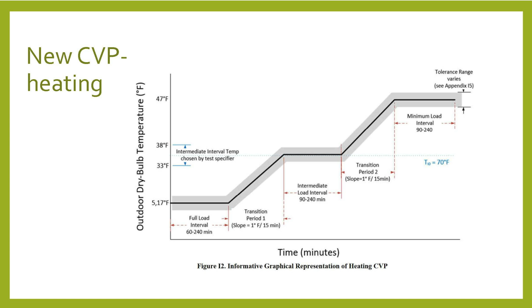This is a huge win. Oh, yeah. This is a big step forward. And the same thing being done in heating. At low temperature, it'll be 5 degrees if they're required to do the 5-degree test. It'll be 17 if they're not calling it a cold climate heat pump. And they'll do high load, low load, and a plateau in between. So we're calling it the 4 corners. High and low on heating, high and low on cooling, as well as checking that it's actually variable speed.